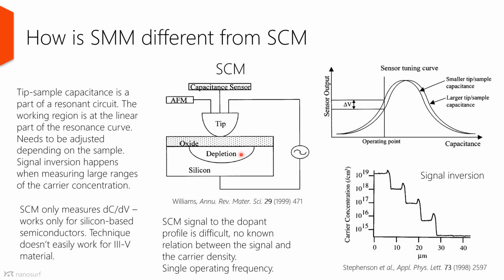In SMM, we measure the S11 parameter, which is a reflection coefficient, and then deduce the capacitance. In the SCM, the capacitance between the tip and the sample is a part of the resonant circuit. There are some parameters that need to be adjusted to find the resonance of the system. And then the sensor is working on the linear region of the resonance curve. In the same way, you modulate the depletion capacitance with the AC voltage applied between the tip and the sample, and you use a lock-in technique to detect the changes in the capacitance while scanning.